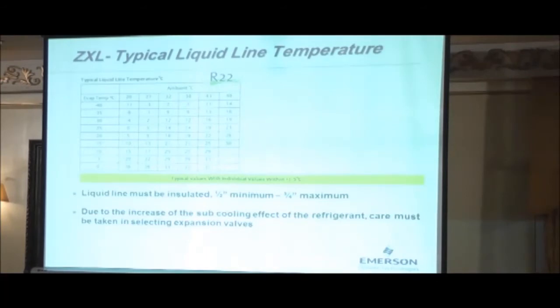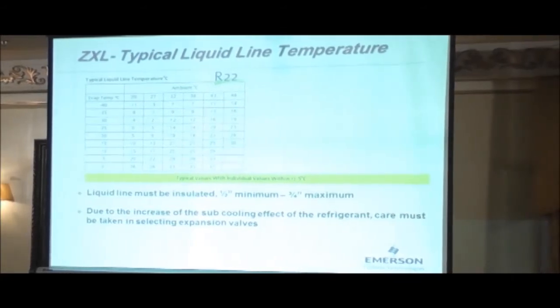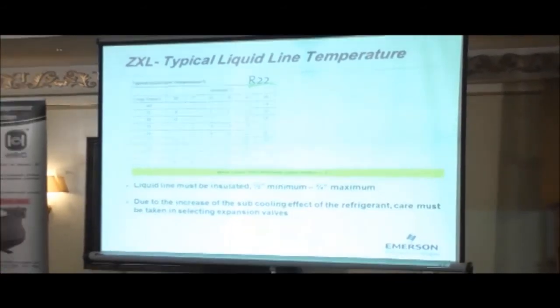So if you use a ZXL unit, it's very important that you insulate the liquid line all the way through to the indoor coil. Right? We want to protect that subcooling. If you do not insulate the liquid line, all that subcooling will be lost, and you're going to have a reduced capacity out of that system. So very importantly, insulate the liquid line. We recommend 1/2 inch to 3/4, whatever is available in the market.